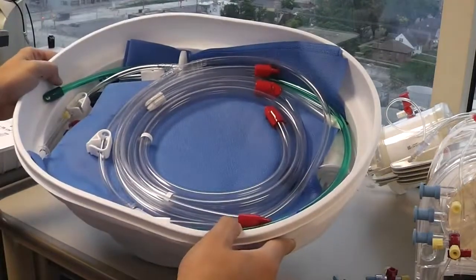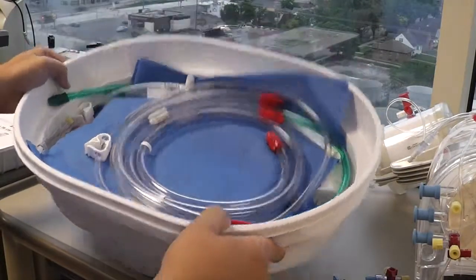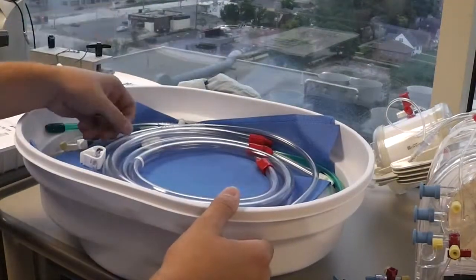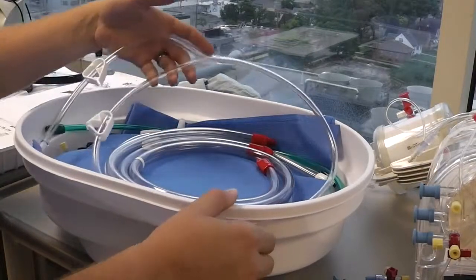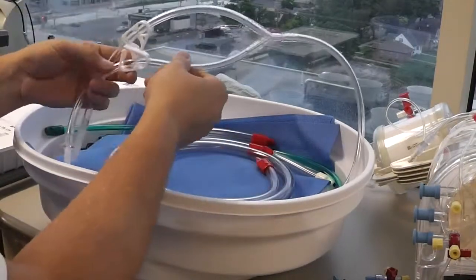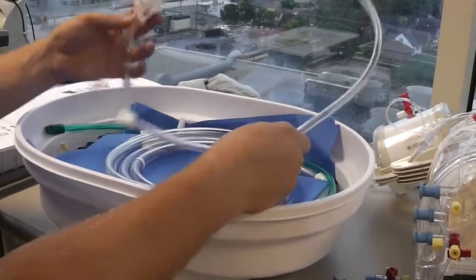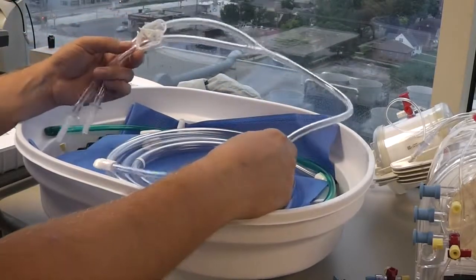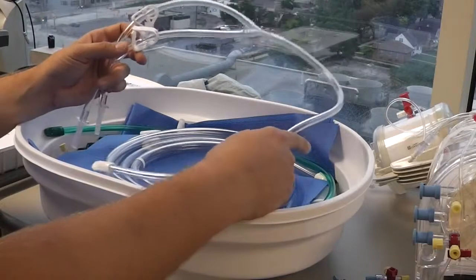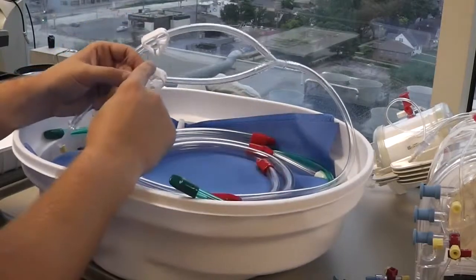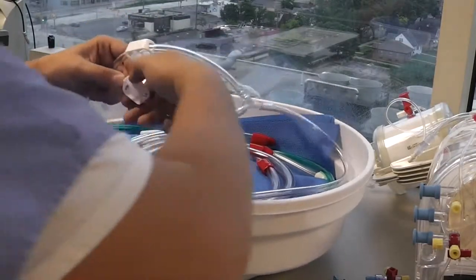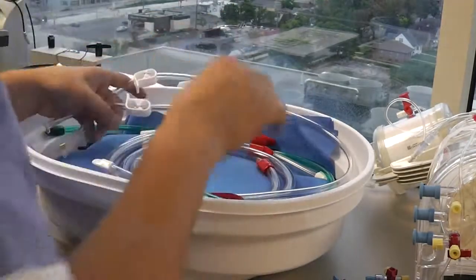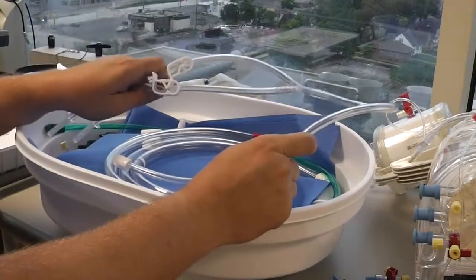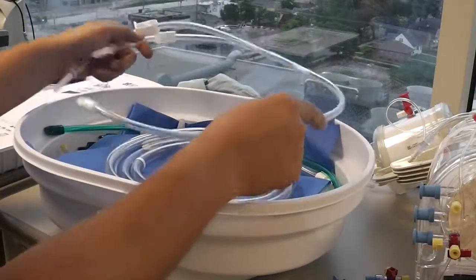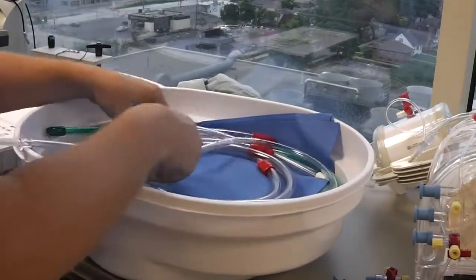But here we have the rest of the tubing pack, and in here there's really not a whole lot we need to do. We basically just need to shut a bunch of duraclamps. So this is the priming tubing that you hang the bags from. Some people close these duraclamps, some people leave them open. I clamp them, but this really doesn't matter. You just have to note when you prime the pump whether these are open or not, so that you know whether the fluid's going to start flowing immediately.